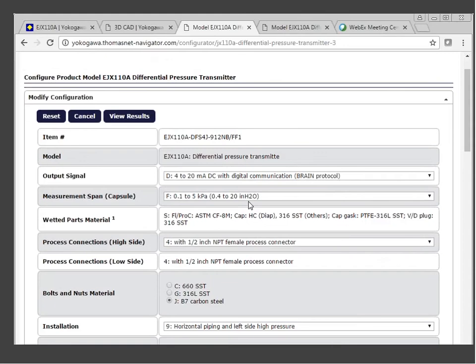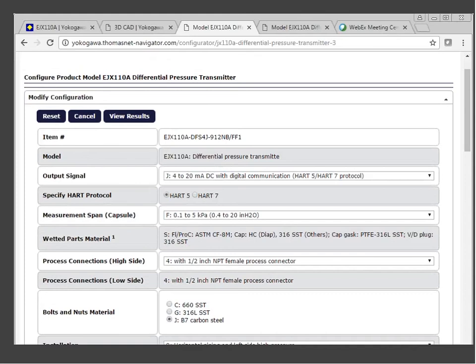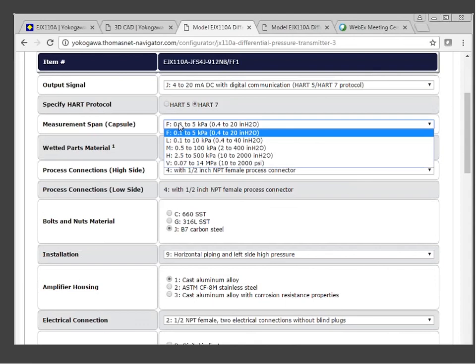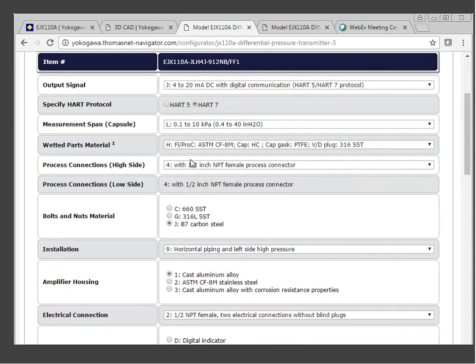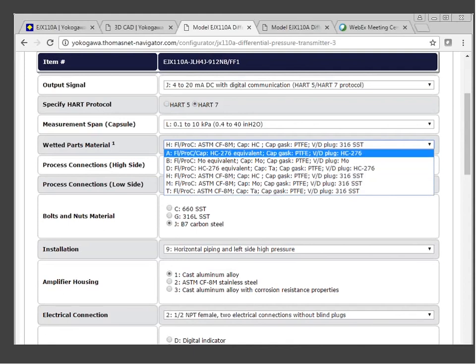We're going to choose without a process connection, do a G, use a 9, do a 1, do a 2, and select a digital indicator. Now, this configuration is set up more like what you would want to put on your PO. When you have the CA option added, on your PO you would want to specify the descriptor, the message, and your software damping. So this is a good feature where anything you need to put on your PO is captured here — it helps you set up your PO correctly.